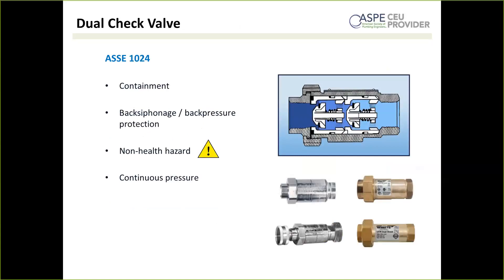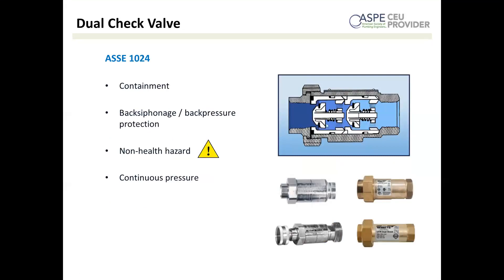ASSE 1024 dual check valves are exactly what they sound like — two check valves, providing built-in redundancy for safety. They allow water in one direction but not the other. These are typically for residential containment and are often installed right after a residential water meter. They are rated for back siphonage and back pressure as well as continuous pressure, but they are not for health hazards. They come in several styles and sizes, including chromed and hose-connection versions.